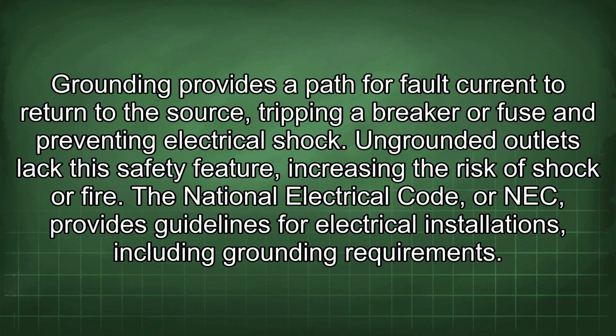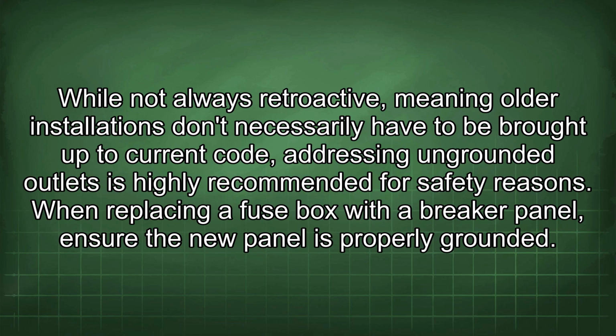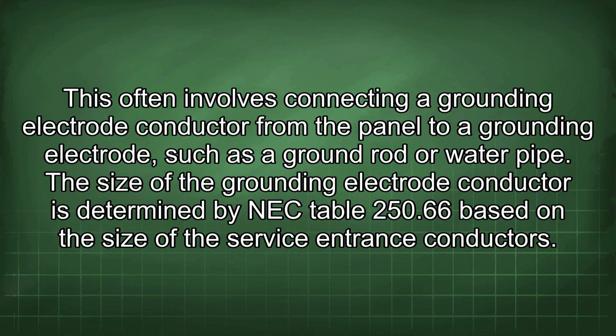The National Electrical Code, or NEC, provides guidelines for electrical installations, including grounding requirements. While not always retroactive, meaning older installations don't necessarily have to be brought up to current code, addressing ungrounded outlets is highly recommended for safety reasons. When replacing a fuse box with a breaker panel, ensure the new panel is properly grounded. This often involves connecting a grounding electrode conductor from the panel to a grounding electrode, such as a ground rod or water pipe. The size of the grounding electrode conductor is determined by NEC Table 250.66 based on the size of the service entrance conductors.